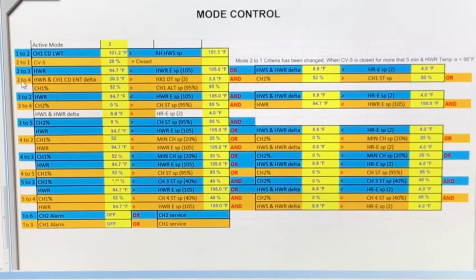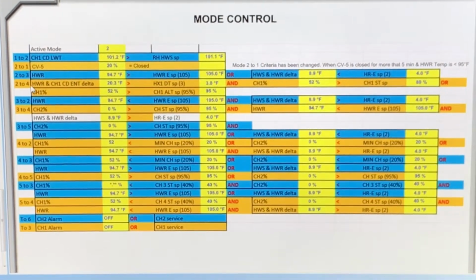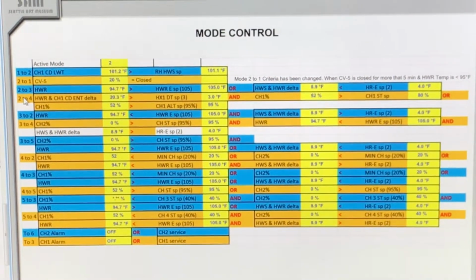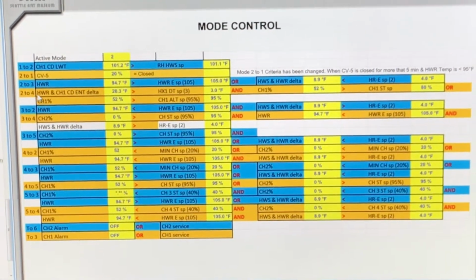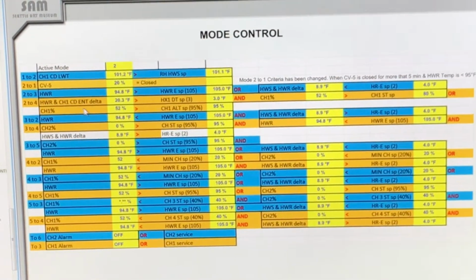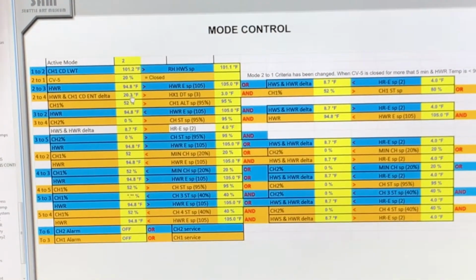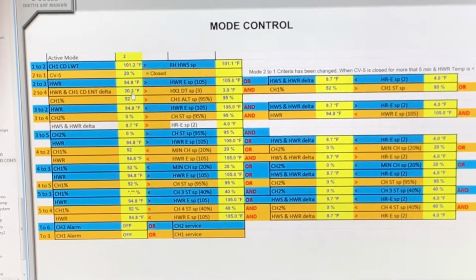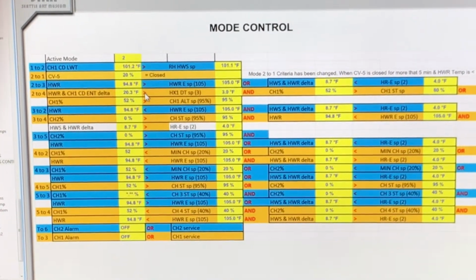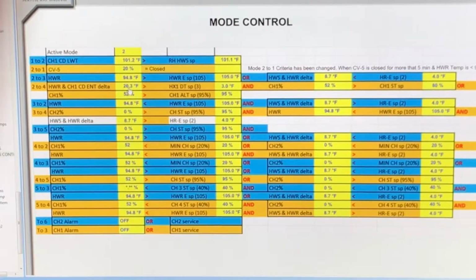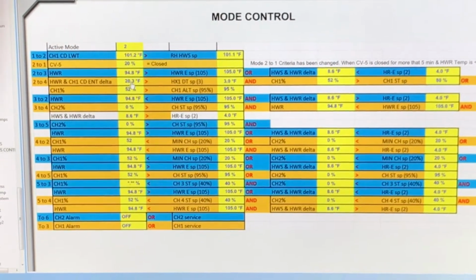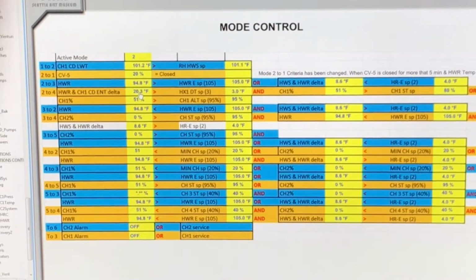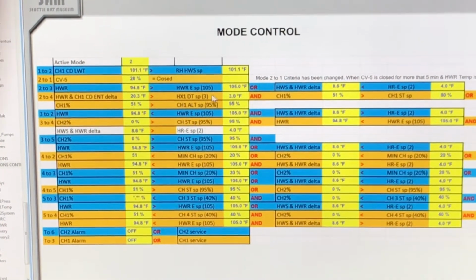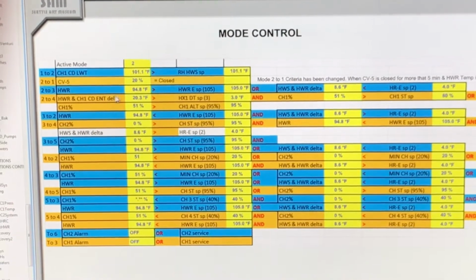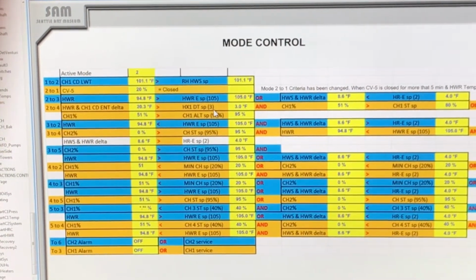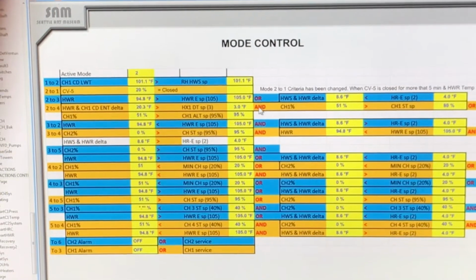And so you've got mode 2 to 4, same type of thing, except it's a little different. The hot water return and chiller 1 condenser entering delta is right now 20 degrees. It has to be greater than 3, which it is. So this condition is true. And this is a very important part of this.